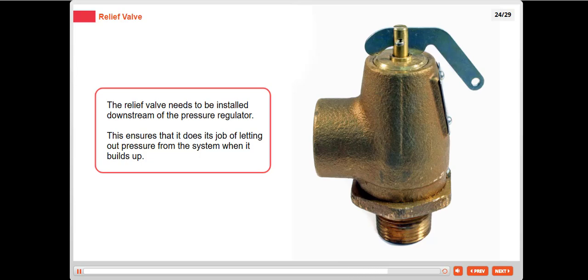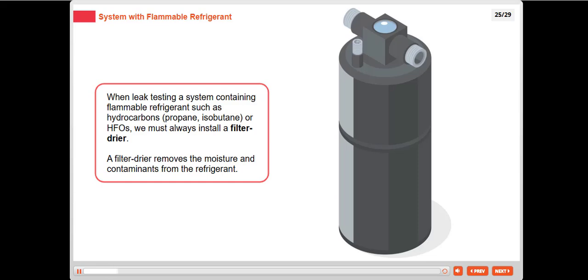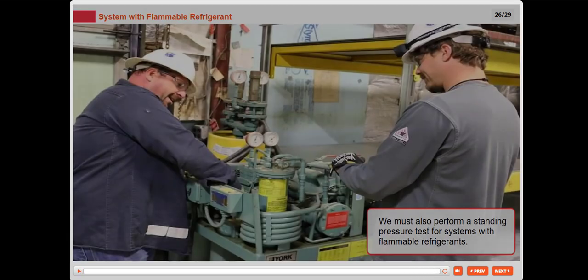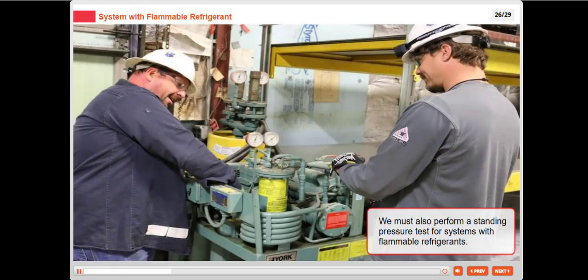When leak testing a system containing flammable refrigerants such as hydrocarbons, propane, isobutane, or HFOs, we must always install a filter dryer. A filter dryer removes the moisture and contaminants from the refrigerant. We must also perform a standing pressure test for systems with flammable refrigerants.